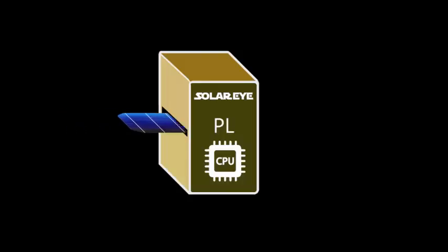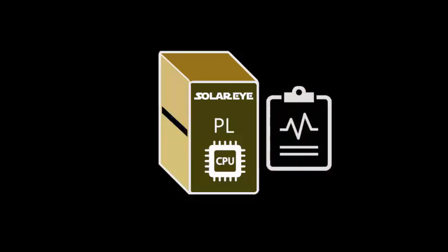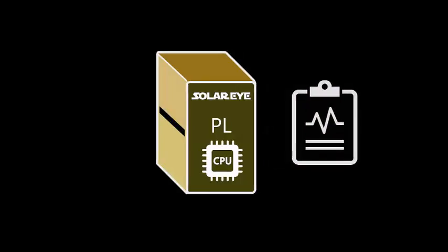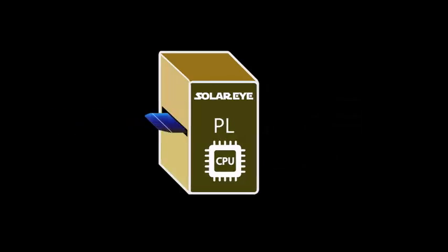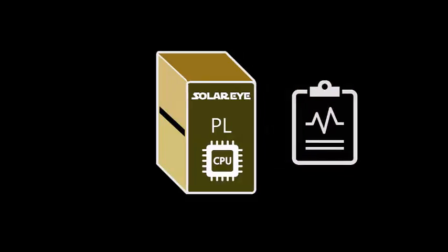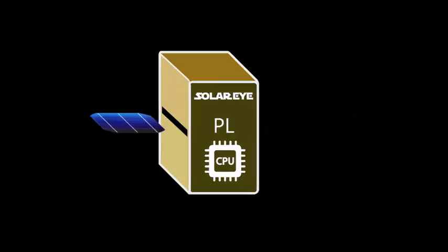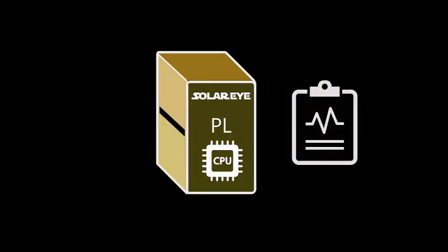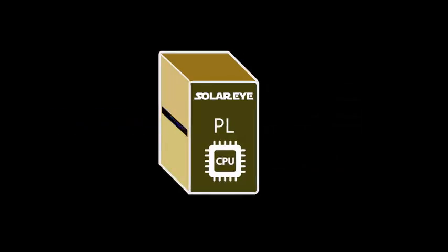Meet SolarEYE, a measurement tool that combines luminescence imaging, IV, resistance measurements, and finite model computation to render rapid diagnosis of each solar cell that points out process-related limitations to cell efficiency and calculates room for improvement compared to the best in class.